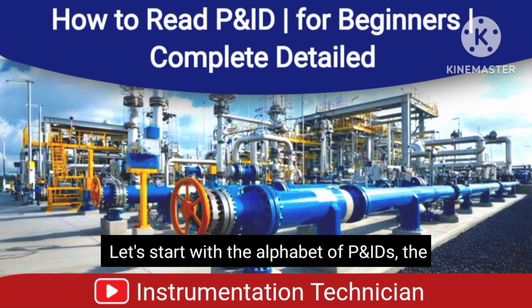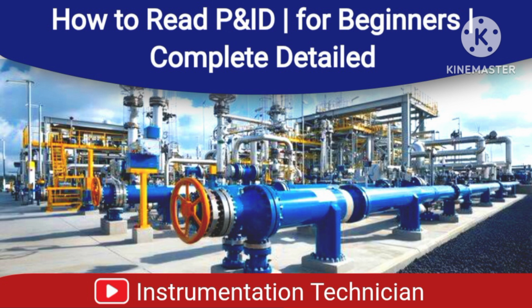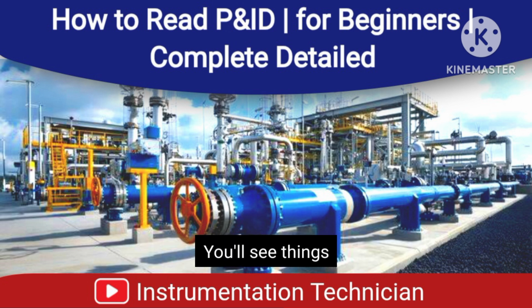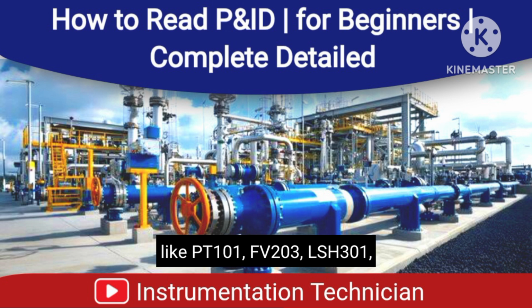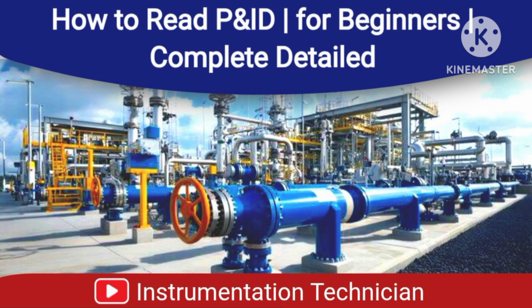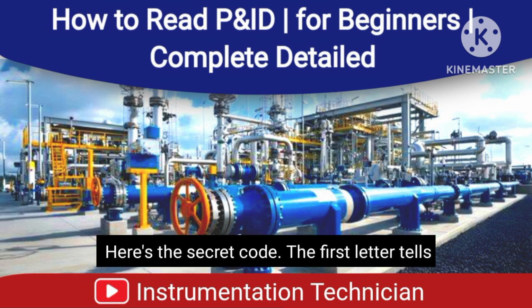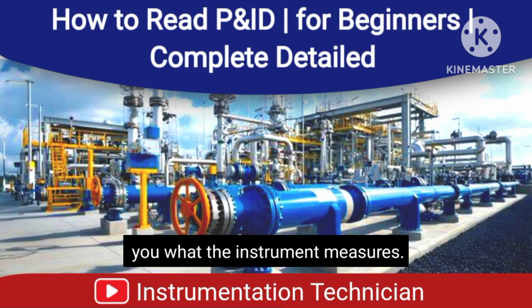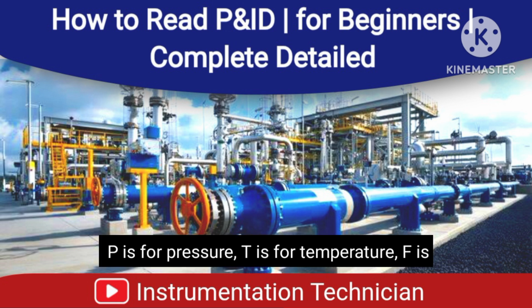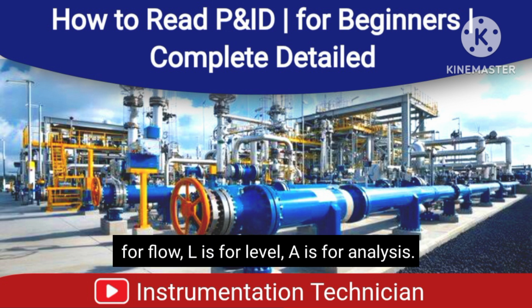Let's start with the alphabet of P&IDs, the instrument tag numbers. You'll see things like PT101, FV203, LSH301. Here's the secret code. The first letter tells you what the instrument measures. P is for pressure, T is for temperature, F is for flow, L is for level, A is for analysis.